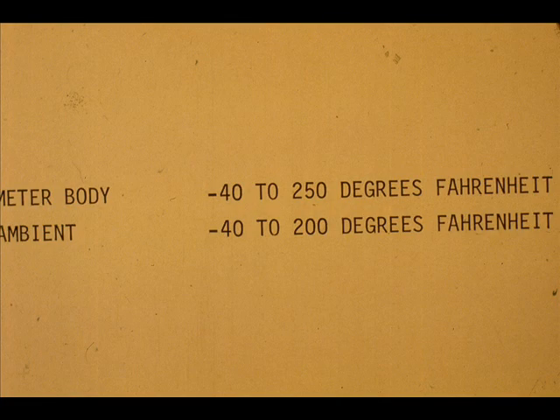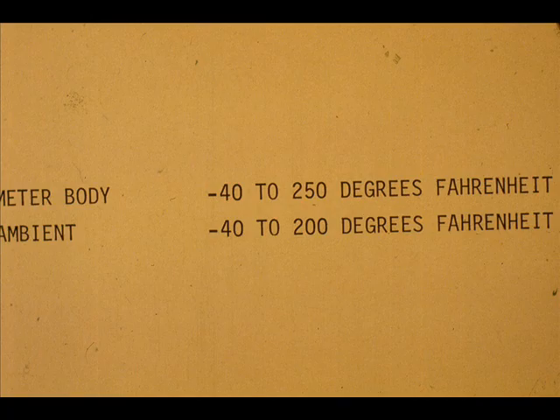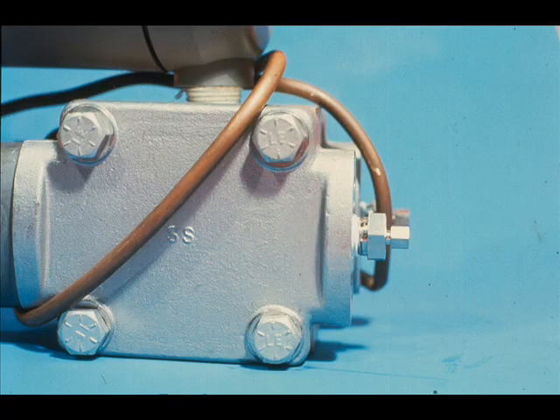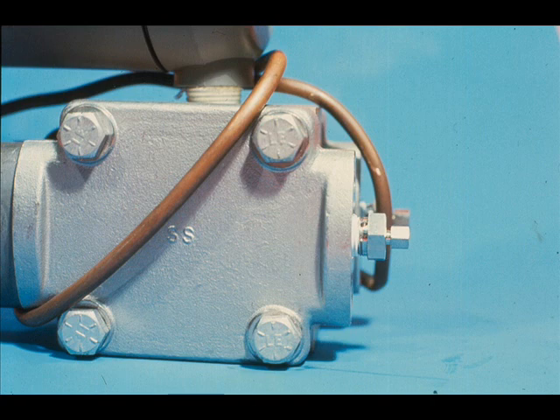The meter body temperature limits are minus 40 to 250 degrees Fahrenheit. The ambient temperature limits are minus 40 to 200 degrees Fahrenheit. This should be kept in mind in the event of an installation requiring steam or electrical tracing.